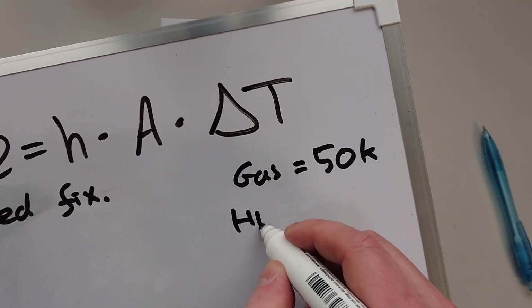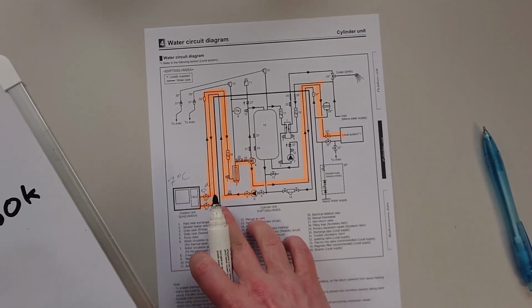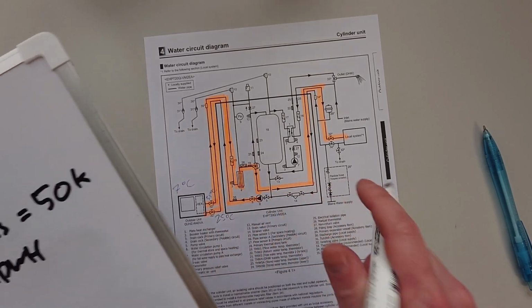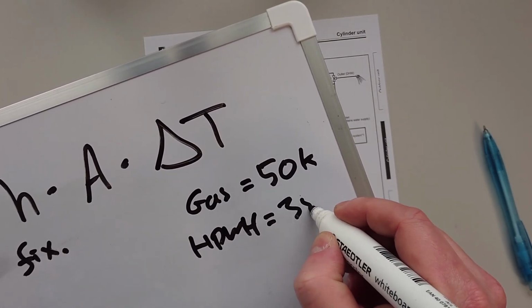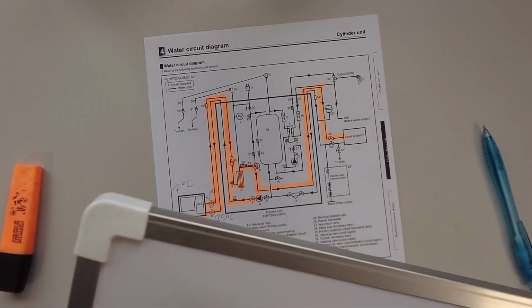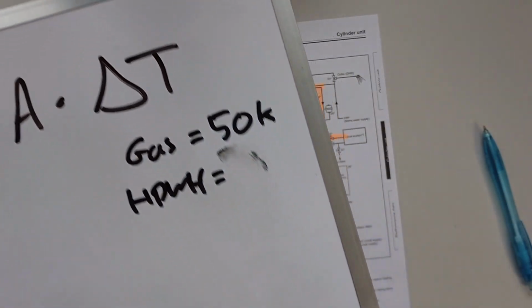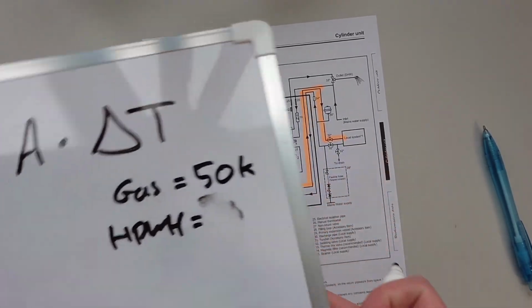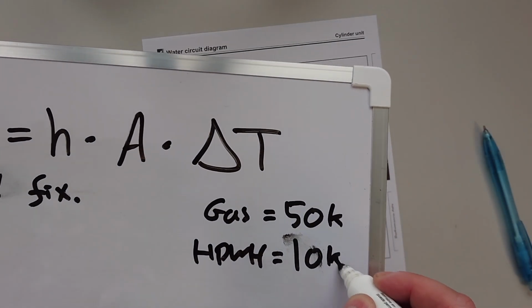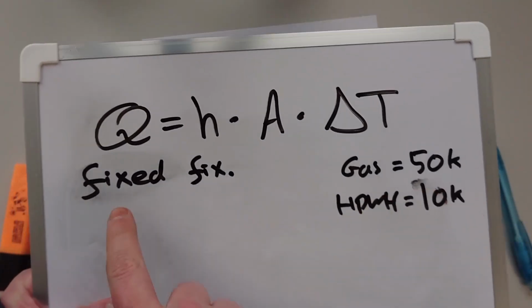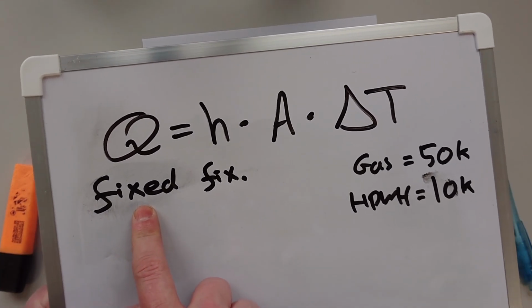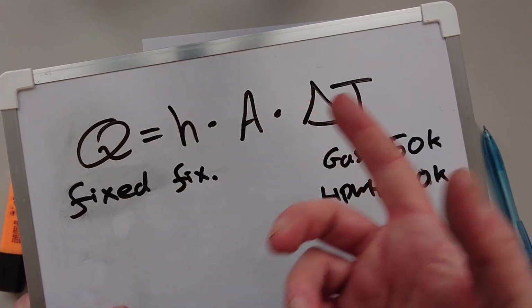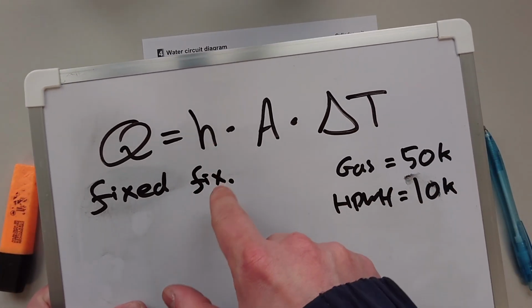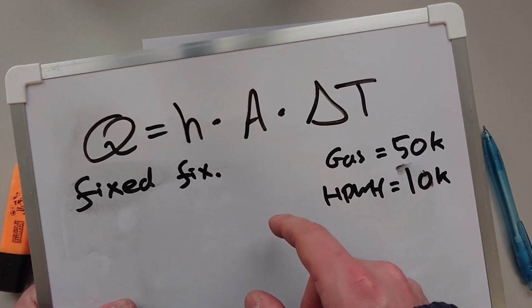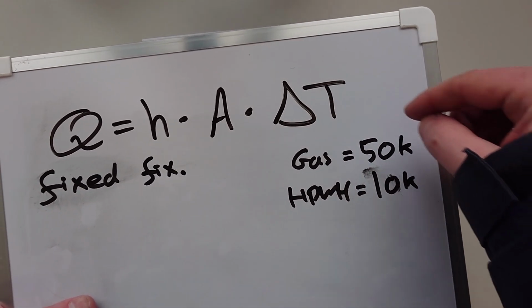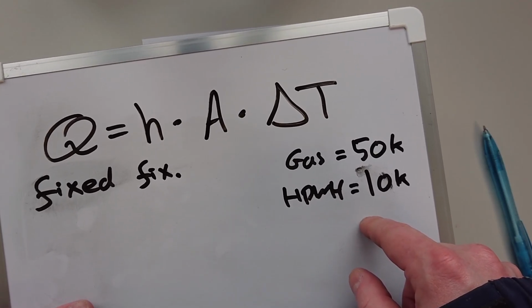But when you use your heat pump water heater, we're coming out at 35 degrees C, not 50 K, coming out of your heat pump and going straight to your radiators. So now we're at 10 K. So what that means is that this heat is fixed, because that's just how much heat it takes to warm your house up, or to keep your house at the right temperature to compensate for the heat that leaks out. Your H is fixed because it's a metal radiator. Your delta T has reduced because we're now pumping water at 35 degrees versus...